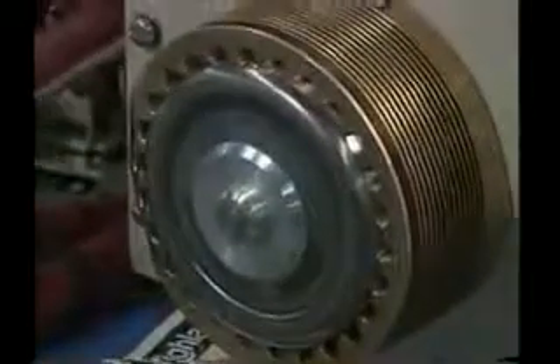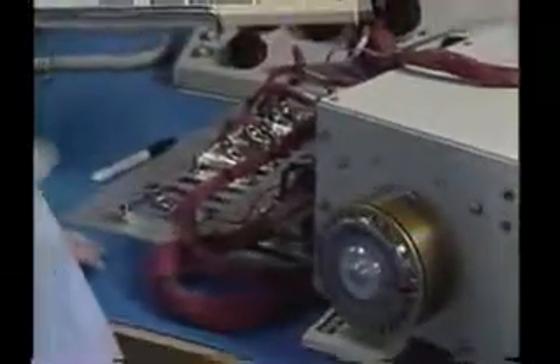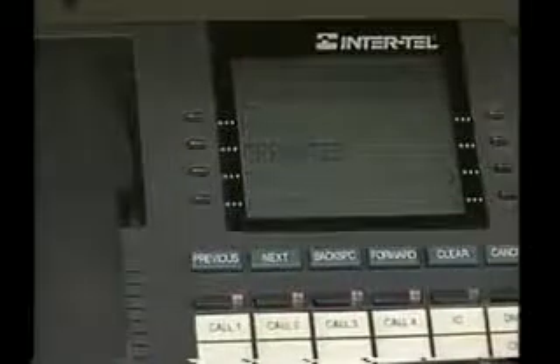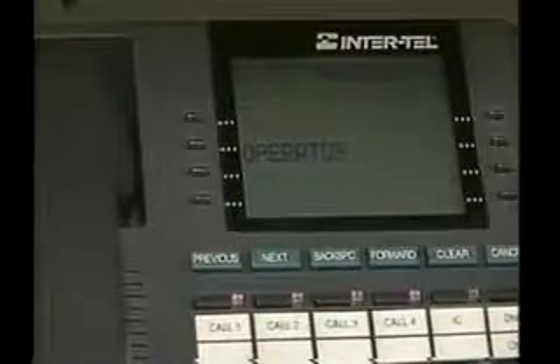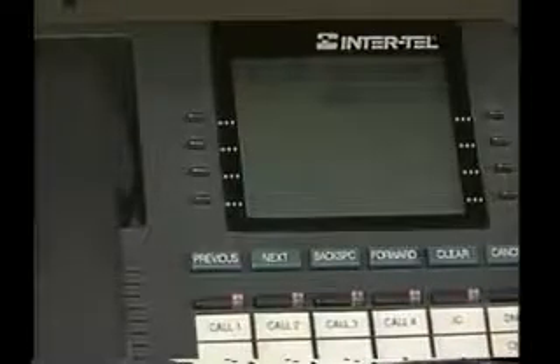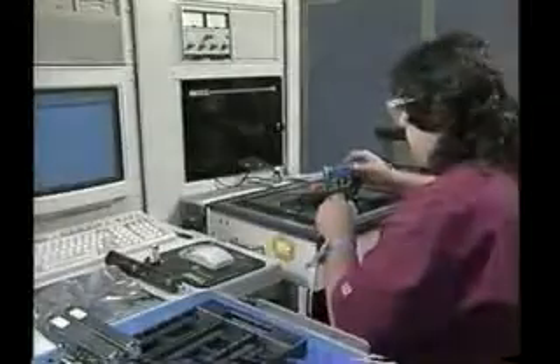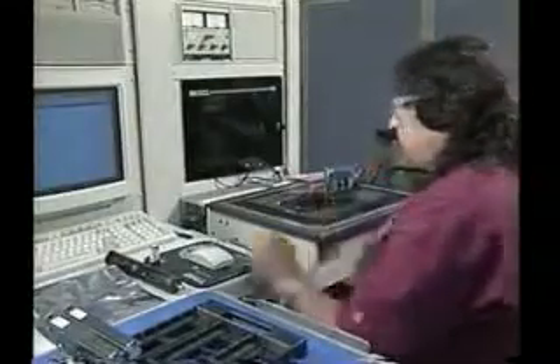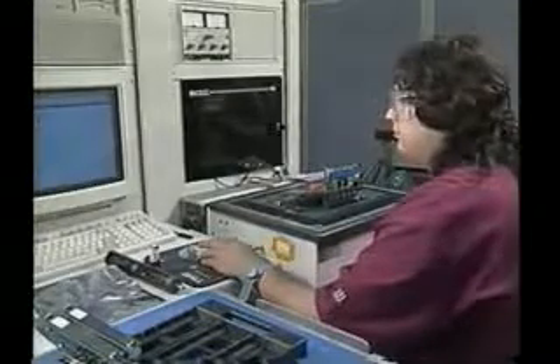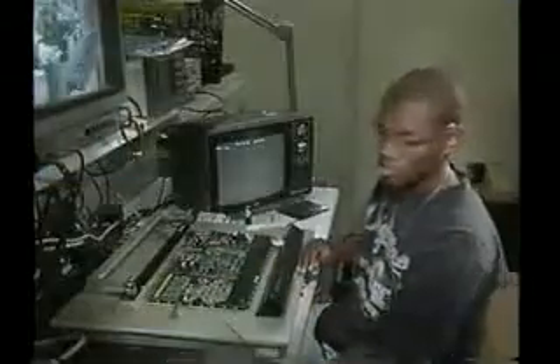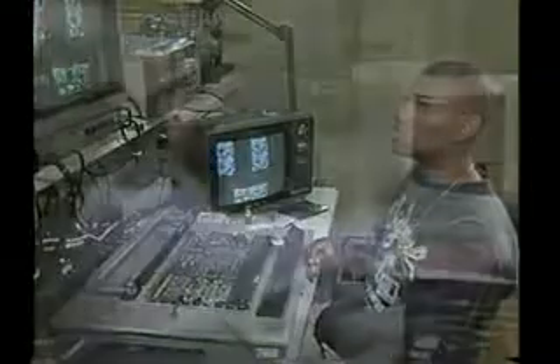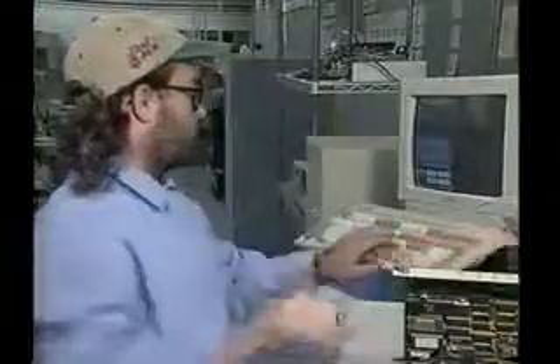As we said earlier, the difference between functional test and ICT is that functional test doesn't check a particular component. It tests the different functions or electronic operations designed into the assembly. For example, because our microprocessor plays an important role in almost all the electronic operations on the assembly, it would be thoroughly exercised and checked during functional test. There are two types of functional assembly level tests. One is done on an automatic test system, and one is performed on a technician's bench with special test electronics. We'll take a look at the automatic test system first.